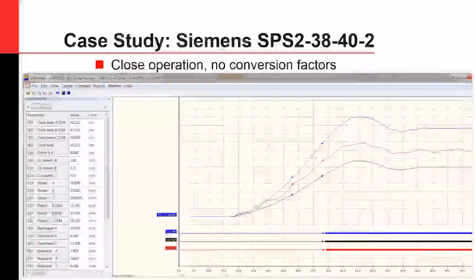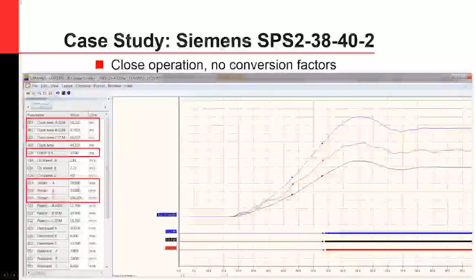So we went through and made a measurement with this, and you'll see, okay, three completely different motion measurements. Although all three of our times are fairly close: 48.2, 47.9, 48.0. So really a difference between phases is only a third of a millisecond. But looking at motion, those are all quite different.